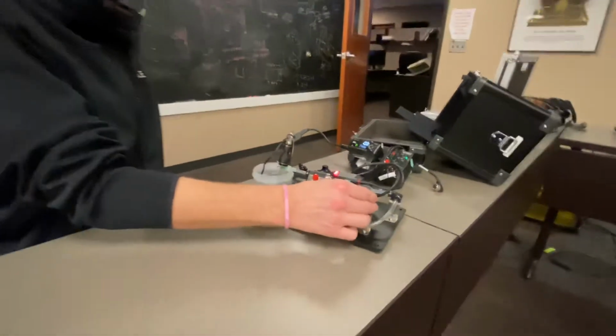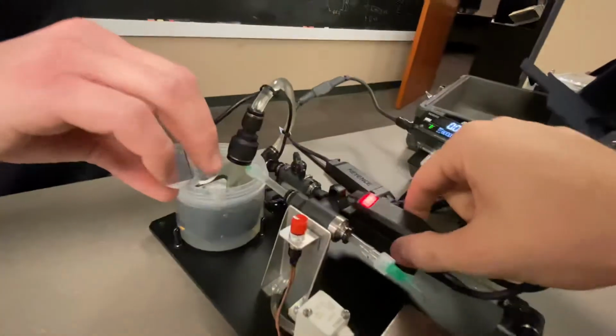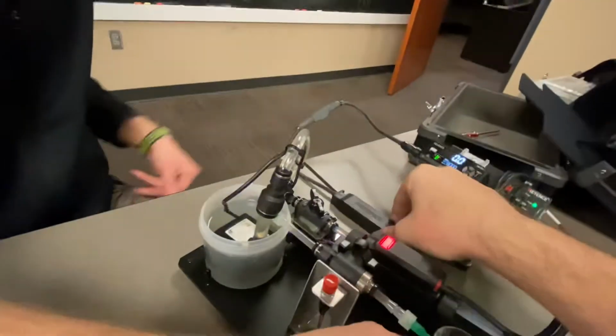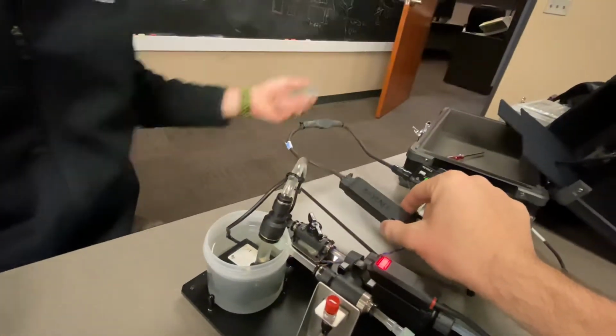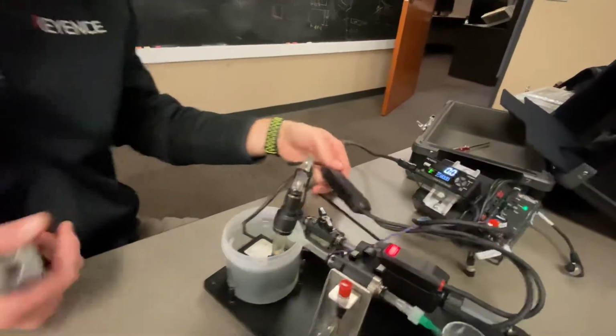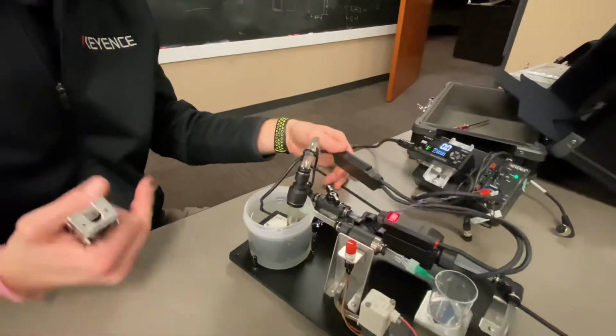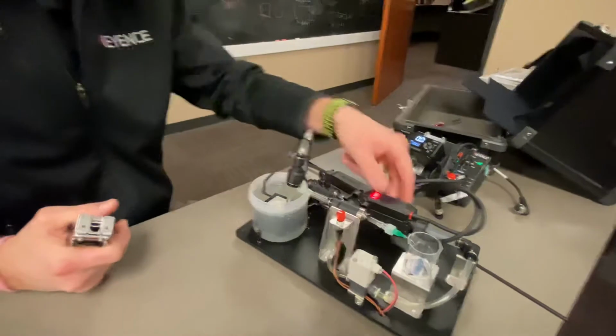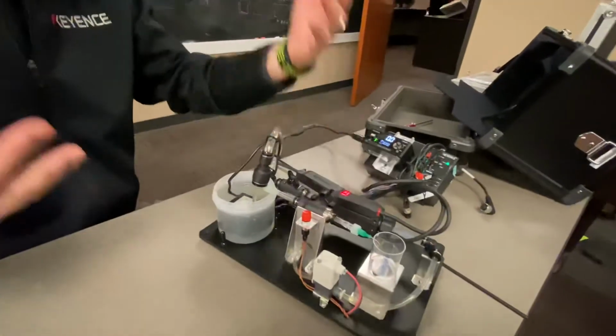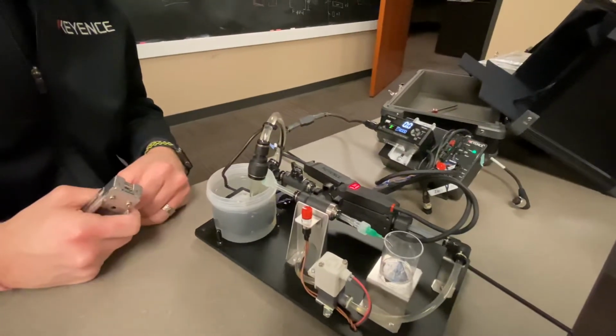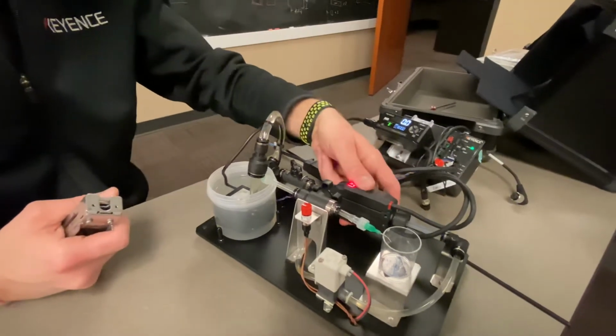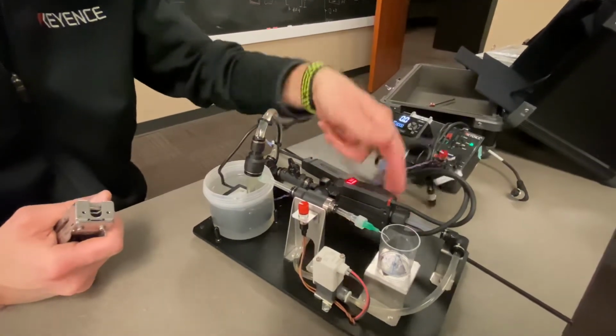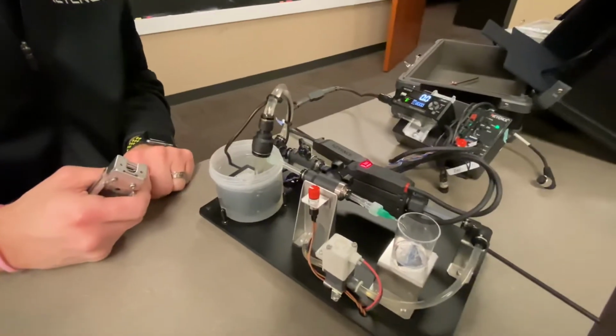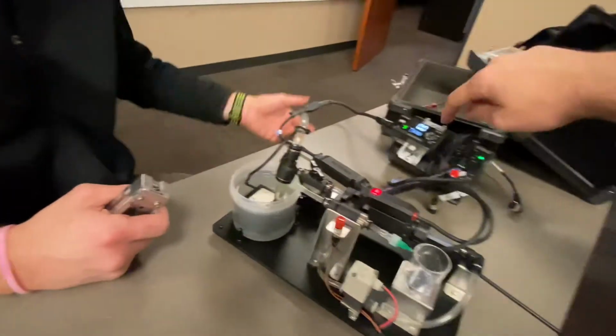And then this is the sensor right here, and this is like a little communication unit - we call it the relay amplifier. What this does is it swallows up the heat, basically, so the flow sensor virtually provides no heat. In some processes it's really heat sensitive, so we don't want to add any heat to the line, especially with some of the smaller lines. And then that goes to the brain here.